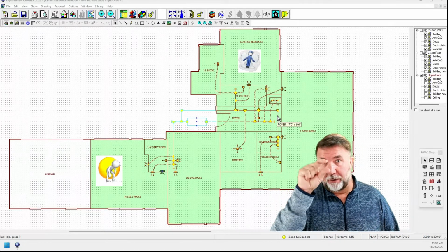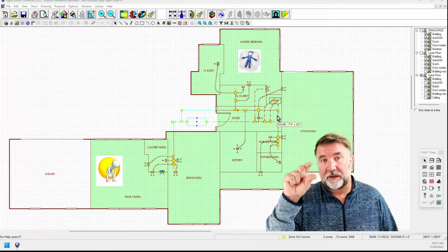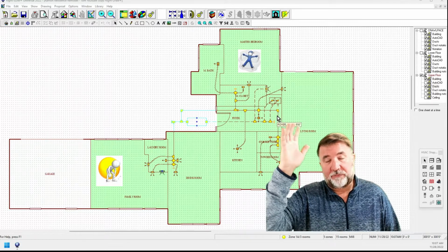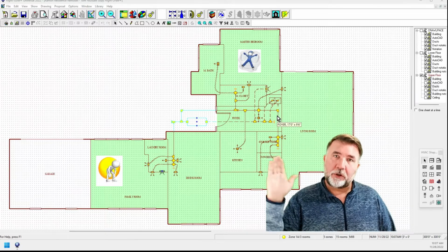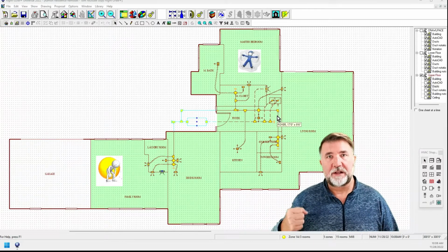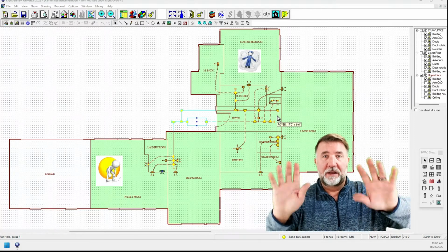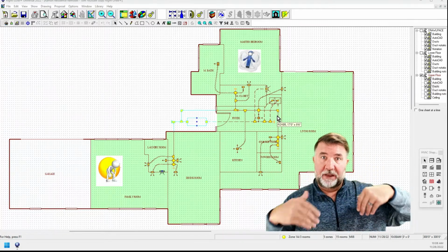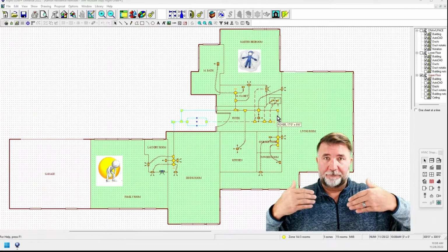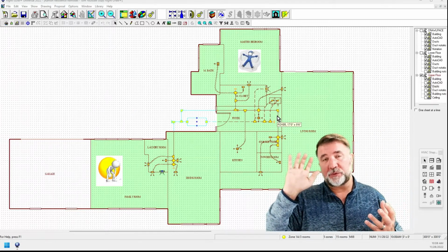Now, everybody knows about the little undercuts under the doors, right? Well, years ago, that was thought to be plenty. We undercut that door, we allow that airflow. And if you don't have a return in your house, and even if you do, go ahead and turn the air conditioner on, close that door, and put your hand underneath the door. You're going to feel that rush of air coming through there. That's the room being positively pressurized with the supply air and pushing that air out. And that's what you're going to feel there. But the problem is if we're not getting enough of that air out, we're not getting that circulation that we need.